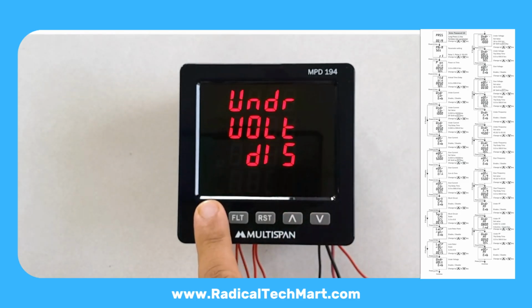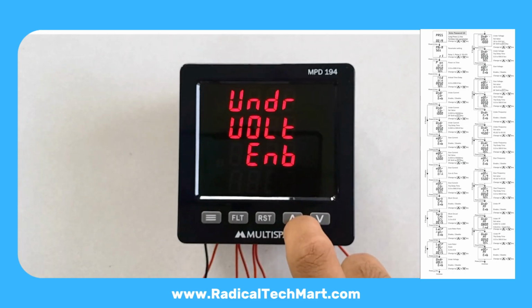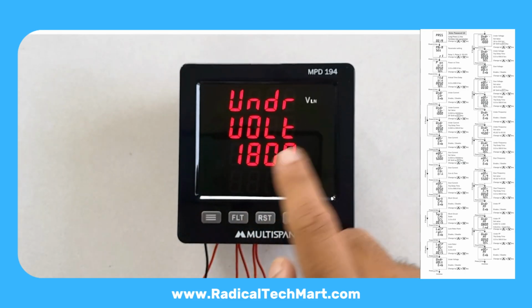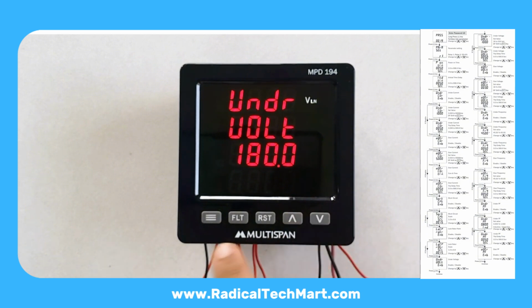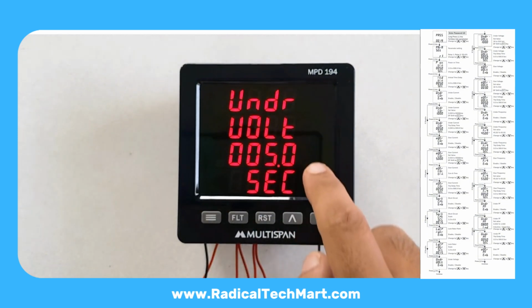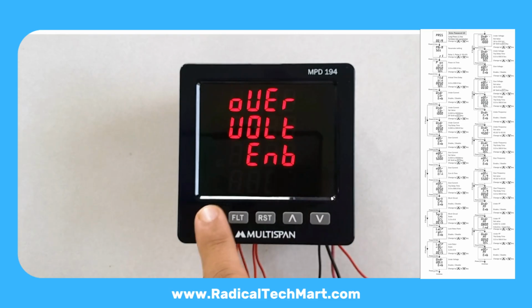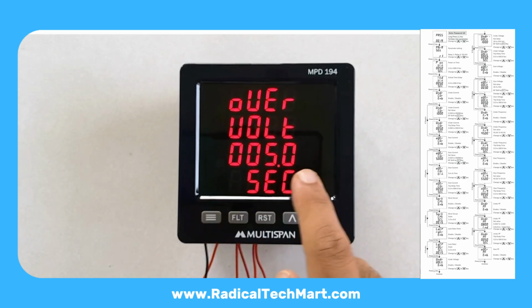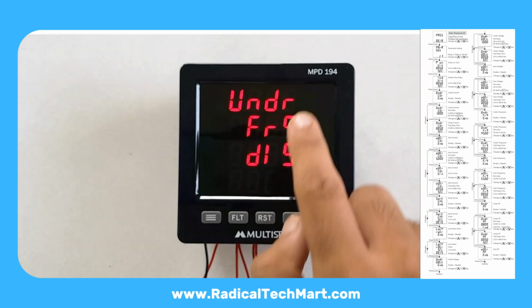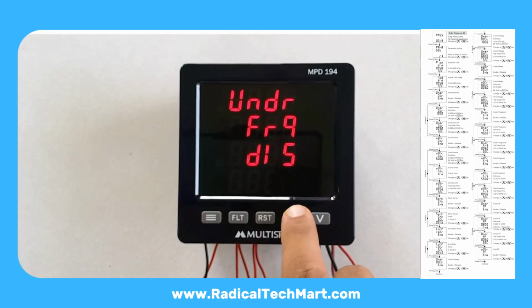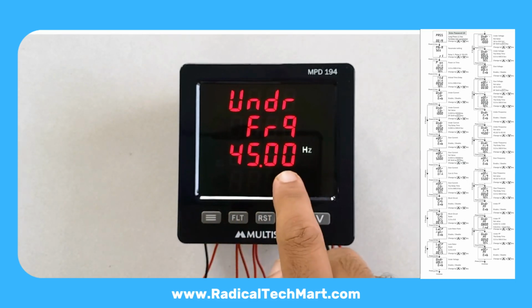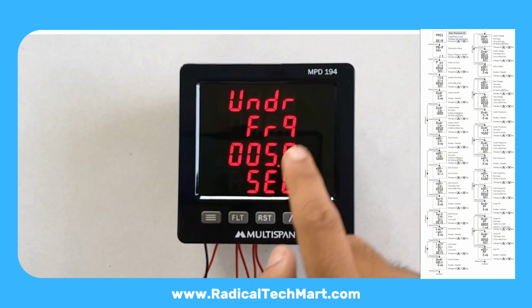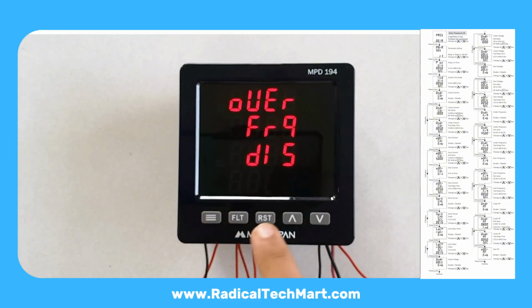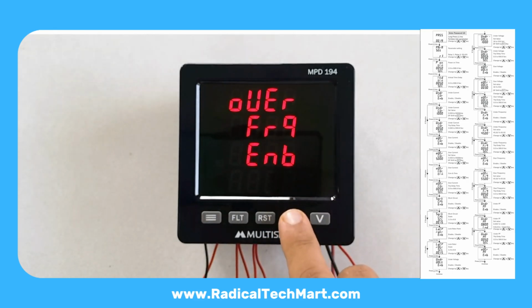Press Set. Now we get under and over voltage. Under voltage: enable, disable. Set under voltage level. Set under voltage trip delay. Over voltage: enable, disable. Set over voltage level. Set over voltage delay. Press Set to move through each. Next, under frequency. Enable, disable. Default 45 Hz. Set under frequency delay. Over frequency: enable, disable. Then set over frequency and its delay.